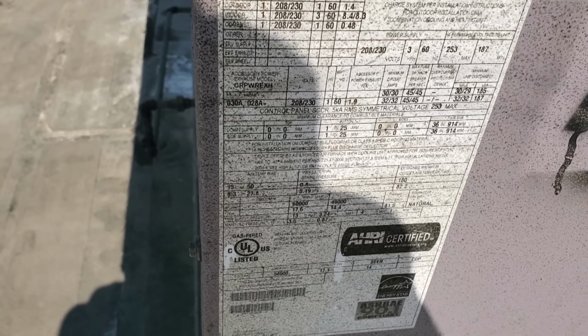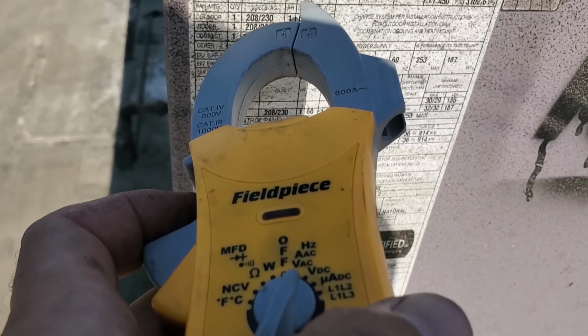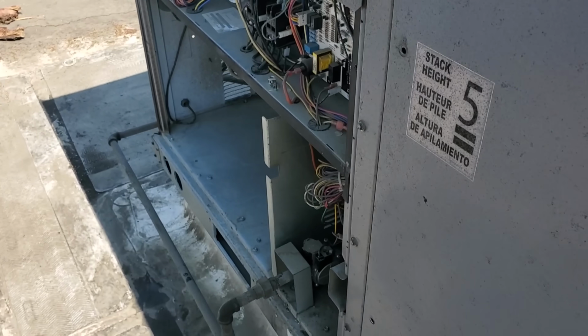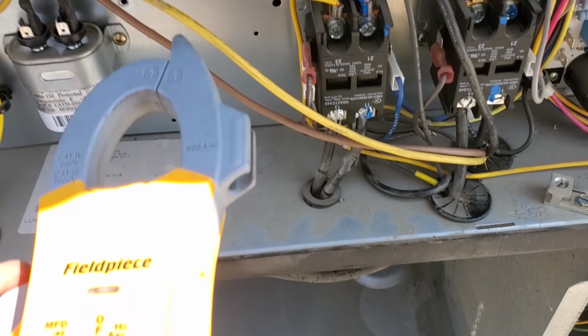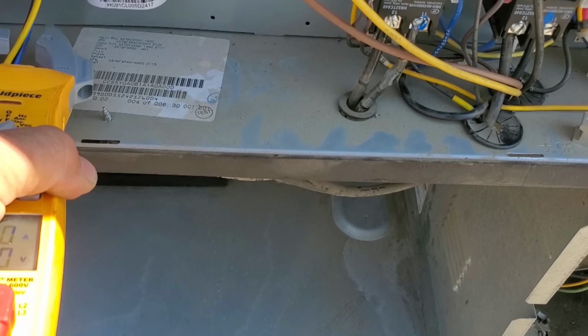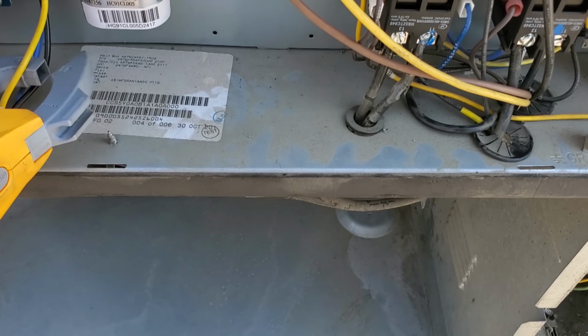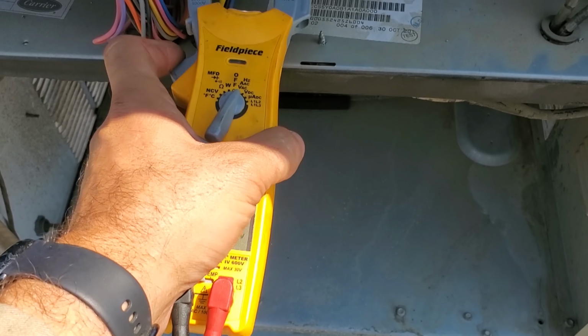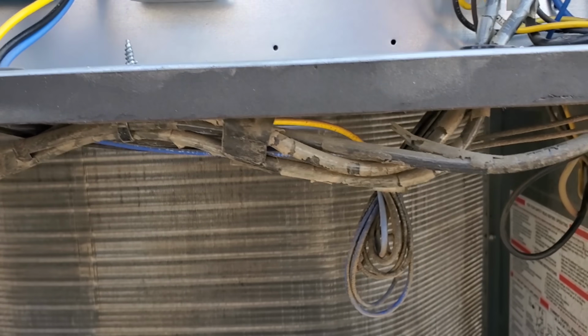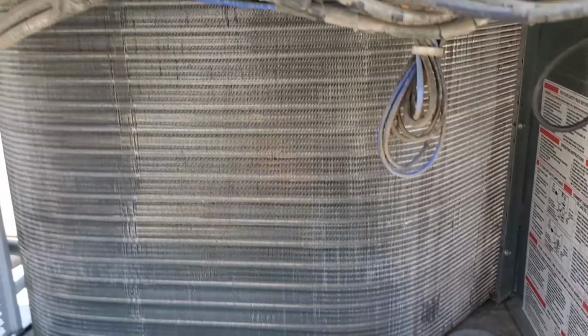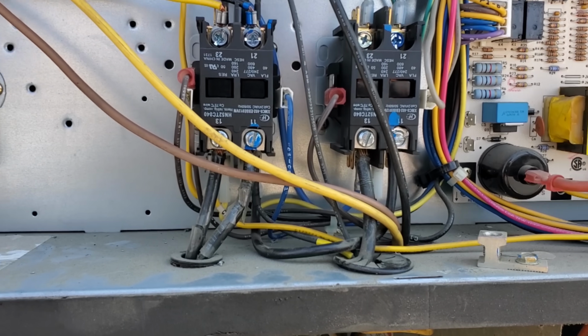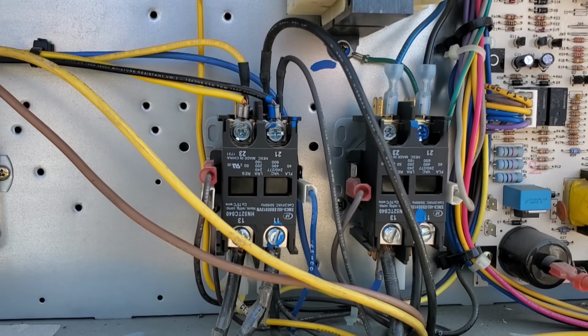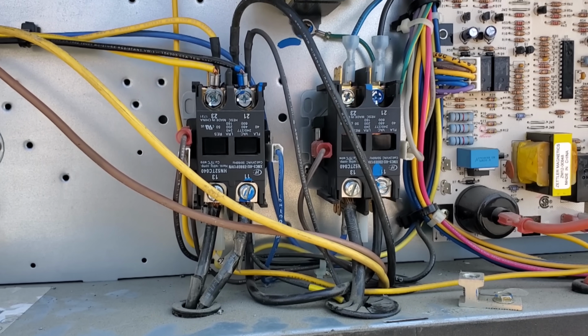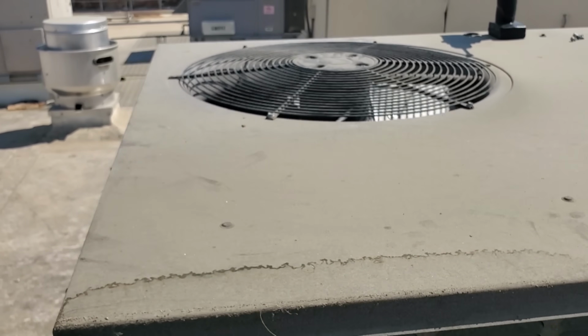Compressor, yeah, that's the condenser motor. Indoor compressor is allowed to run 15.9. 15.9, we could get that guy right here. Let's see what this guy's doing. Yeah, we're not even running anywhere near full load on the compressor. I'm not seeing anything with this. I have no voltage drop across the contactors. Everything's looking good. I don't see a reason for the breaker to trip.